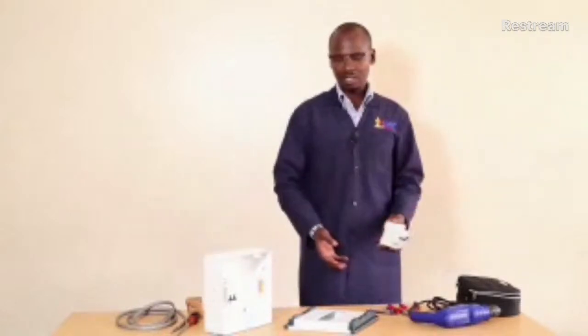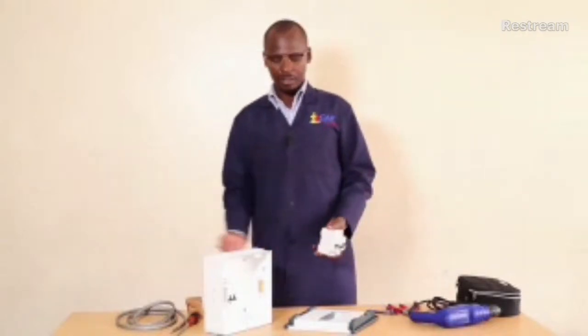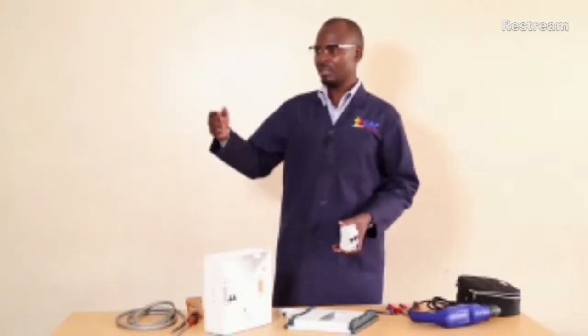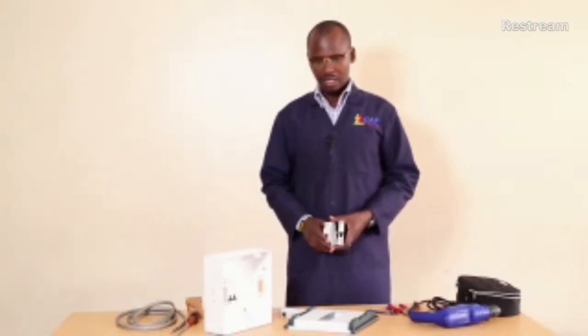So in a simple domestic installation, we'll have lighting points, we'll have socket outlets, and probably the cooker, or maybe an instant shower. So lighting points, when you install ordinary bulbs, the fuse rating is supposed to be between 5 amps to 10 amps. That will work well with the lighting points. And for the socket outlets, you will need 32 amps. This will help because maybe you'll be charging a lot of things, you are using electronics, and maybe still you are using it for ironing. So you need 32 amps to regulate that line. And probably you have the cooker control system, which also needs a lot of current or voltage. You'll also regulate it using 32 amps.